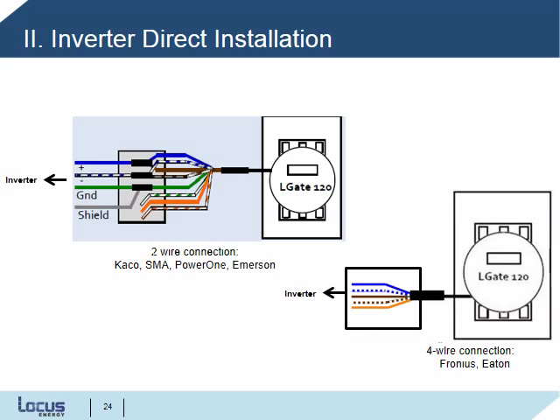Here we have the two common RS-485 wire connection methods for inverter direct monitoring, 2-wire and 4-wire. We'll be using the blue, blue-white, brown, and brown-white wires, which translate to the RX and TX positive and negative ports on the LGate 120. For 2-wire inverters, crimp the blue with brown and the blue-white with brown-white. From here, the blue, blue-white, and green wires should be connected to inverter positive, negative, and ground.